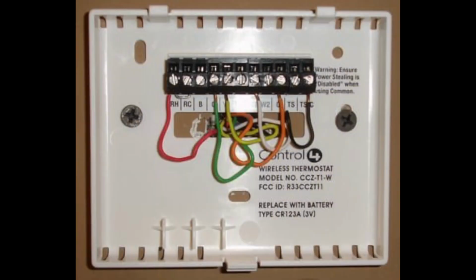The next one you're looking at, this is the back part of a standard thermostat. This one here, it says look down in the middle, it says control wireless thermostat module number CCZT1 and stuff like that. It even has a way on this one where it's wireless thermostat, but this one is wired in to the unit. And we're going to start from the left-hand side where it has RH, RC, B, C, Y, W, W2, O, TS, and then TS. So this hookup you have here, if you have a home that has a heat pump, this is the wiring at the thermostat for a heat pump.